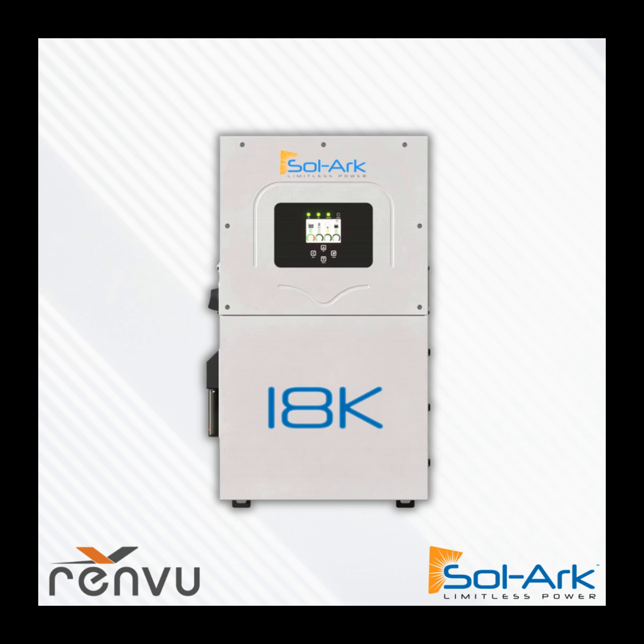So with the 15K inverter, it was 15 kilowatts of AC output, but only with solar. The nameplate on the Sol-Ark 15K for the battery component was 12. If you are familiar with the 15K, you'll know that 12 kilowatts was a very conservative spec, because when you looked at our 275 amp charger times 51 volts, volt times amp is watt, and that's more like 14 kilowatts. We conservatively spec'd out the 15K to say, from the top of the battery range to the bottom of the battery range, you can rely upon 12 kilowatts of power.